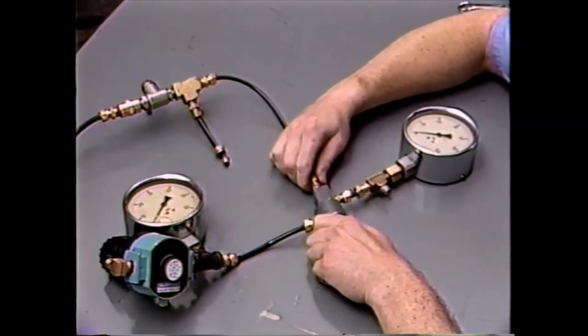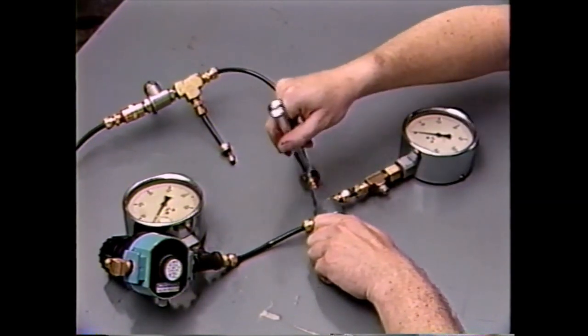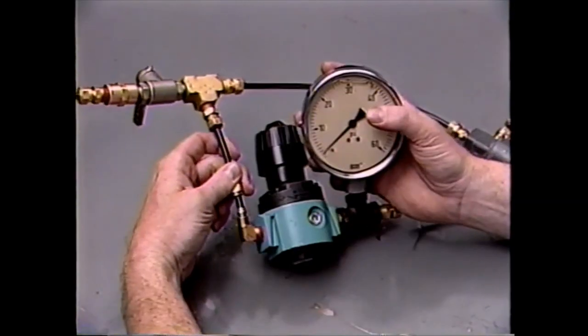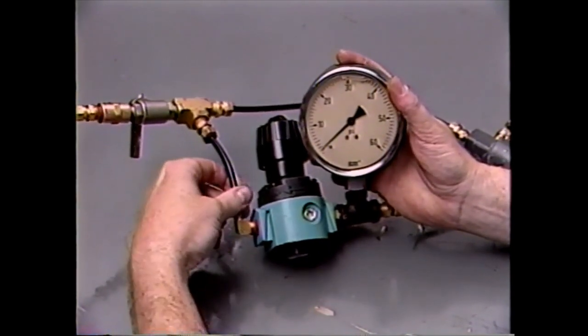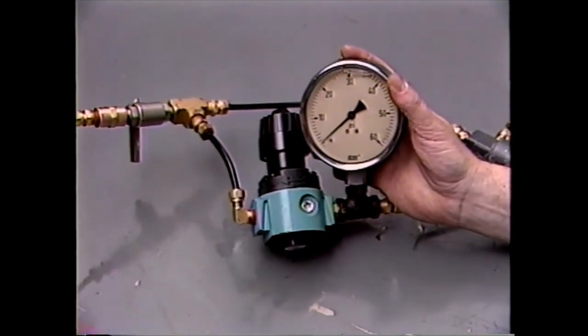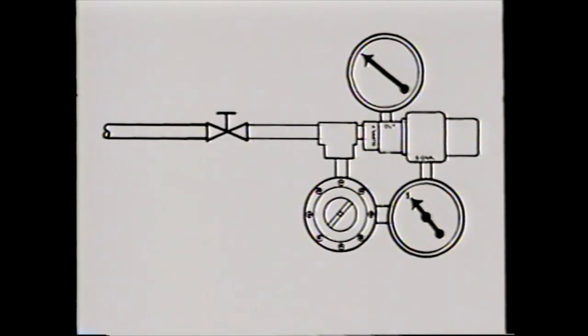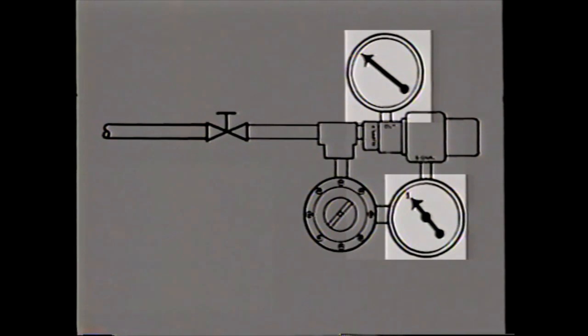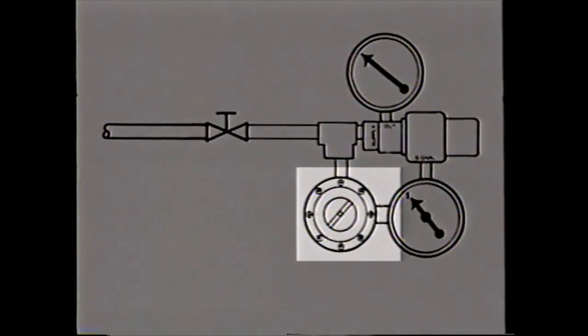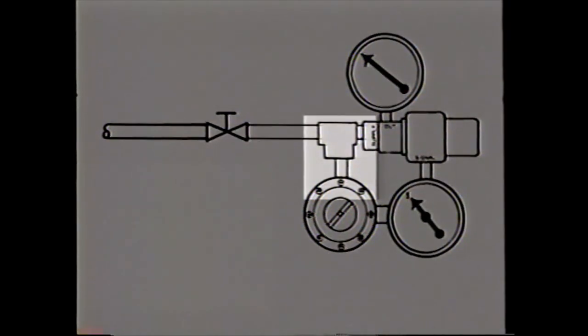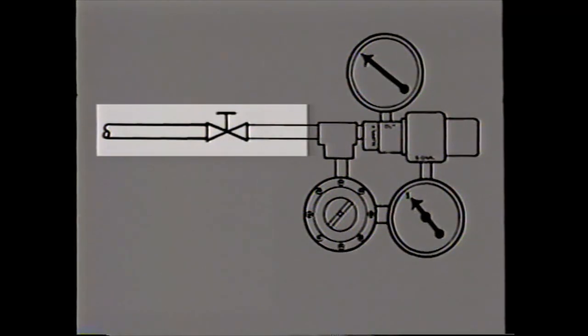Connect a shop airline containing a shutoff valve and T to the supply port on the valve. Also connect an airline from the T in the supply line to the regulator. In case you missed some of the connections, here's a diagram of what this test setup looks like. Here are the gauges attached to the outlet and signal ports. The pressure regulator connects to the signal port gauge, and a T attaches the supply port on the relay to the pressure regulator and the shop airline containing the shutoff valve.